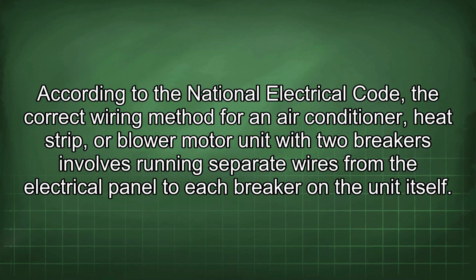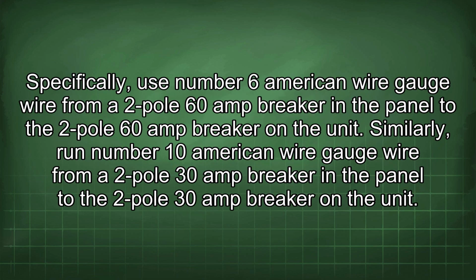According to the National Electrical Code, the correct wiring method for an air conditioner, heat strip, or blower motor unit with two breakers involves running separate wires from the electrical panel to each breaker on the unit itself. Specifically, use number 6 American wire gauge wire from a 2-pole 60-amp breaker in the panel to the 2-pole 60-amp breaker on the unit. Similarly, run number 10 American wire gauge wire from a 2-pole 30-amp breaker in the panel to the 2-pole 30-amp breaker on the unit.